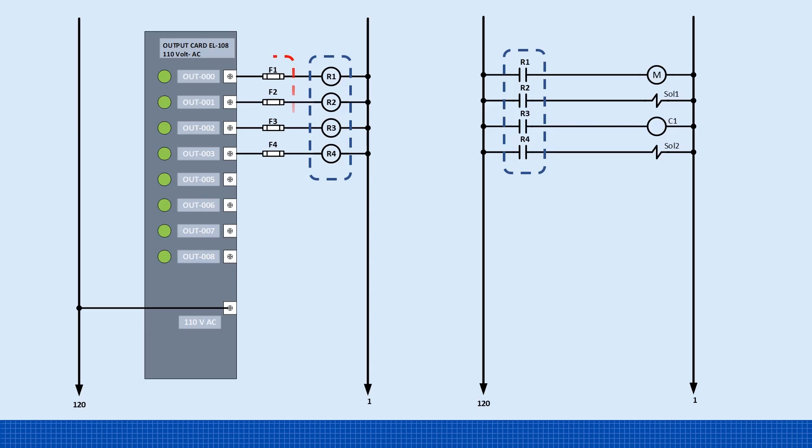And here's an important best practice. Always fuse the PLC output that powers the relay coil. If the coil ever shorts out, a properly sized fast blow fuse will trip instantly, protecting your PLC output.